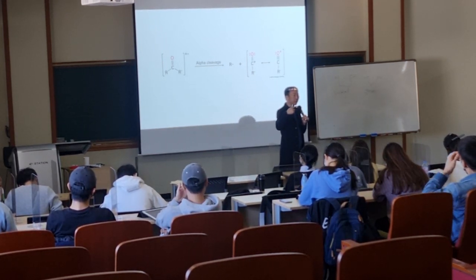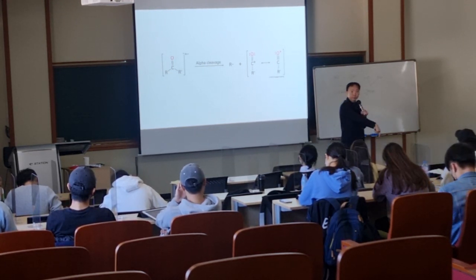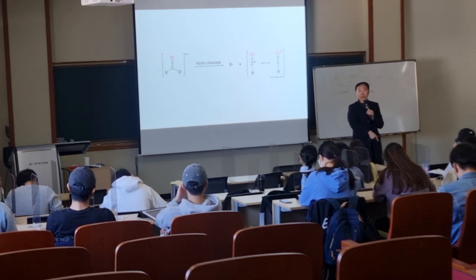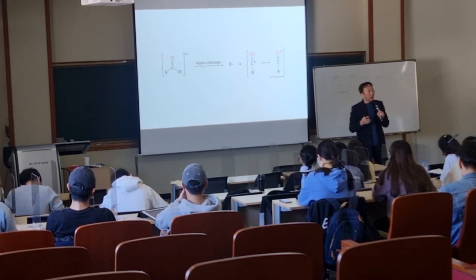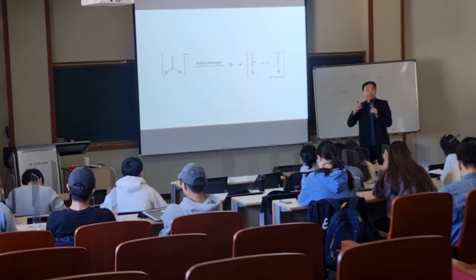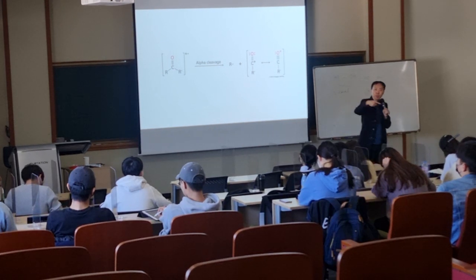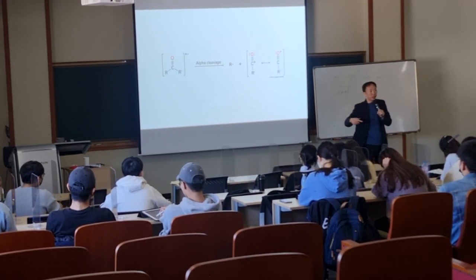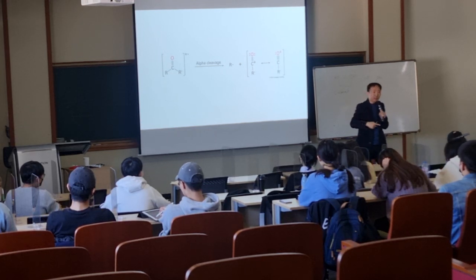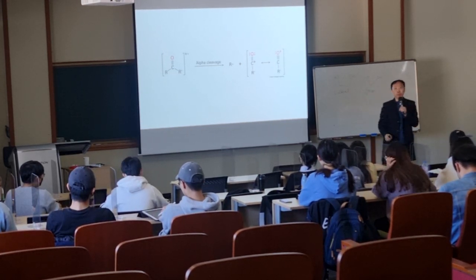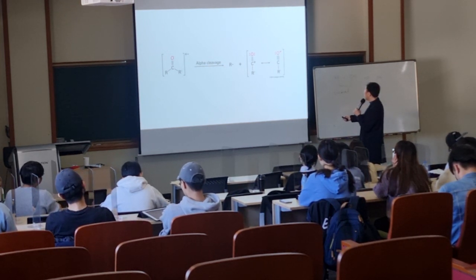Then it has a force that makes it move in a circular motion. That is the mechanism. That's why, to get mass data, you need to ionize your molecules, either negatively charged or positively charged. Positive charges travel this way, negatively charged travel this way. Only with that difference, this angle and distance can give you the information of molecular weight. Okay, that's why in this case only you can see this part.